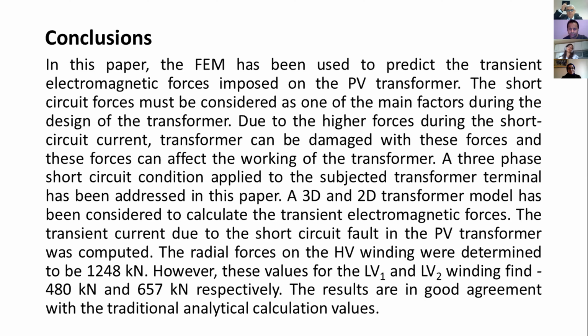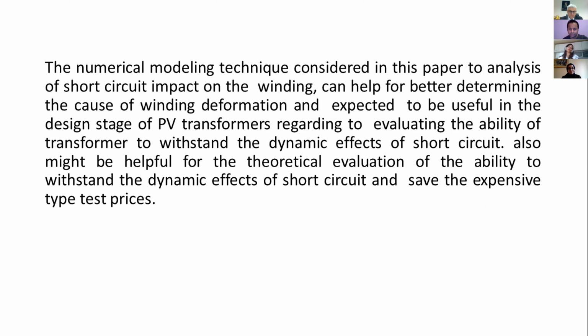The numerical modeling technique considered in this paper to analyze the short circuit impact on the winding can help in better determining the cause of winding deformation, and is expected to be useful in the design stage of photovoltaic transformers. Regarding evaluating the ability of a transformer to withstand the dynamic effects of short circuit, it might also be helpful for the theoretical evaluation, and can save the expensive type test prices.